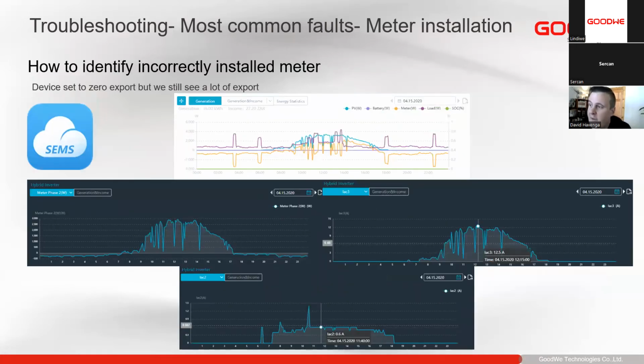So here's an example where the phase rotation caused a problem for a customer. This customer installed the inverter, rectified the phase rotation, and set export power limit on and to 0 with the unbalanced output enabled. The unbalanced output of our ET inverters enables individual phase limiting. So if the smart meter's connections are not the same as the inverter's connections, that leads to this problem.